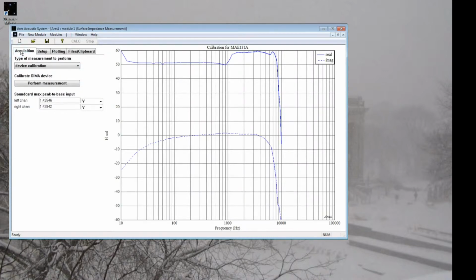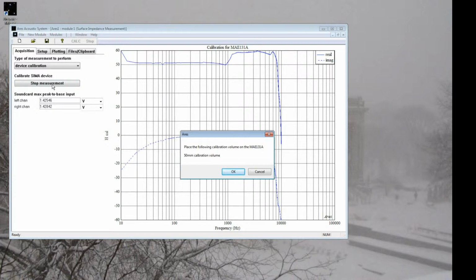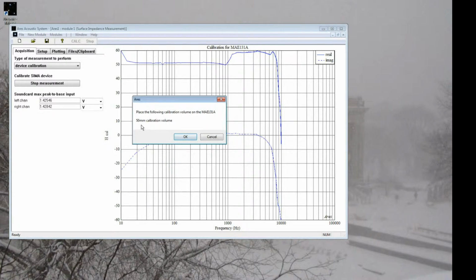Going back to the acquisition tab, there are two types of acquisitions that can be done: a device calibration and an impedance measurement. So we're going to start off by doing a device calibration of the 131. When we're done, we're going to get a new calibration curve, and these maximum sound card inputs will be updated as well. So I'm going to hit perform measurement. Ares will communicate with the control electronics, and it asks us to place the 50 millimeter calibration volume on the 131 so we can proceed.